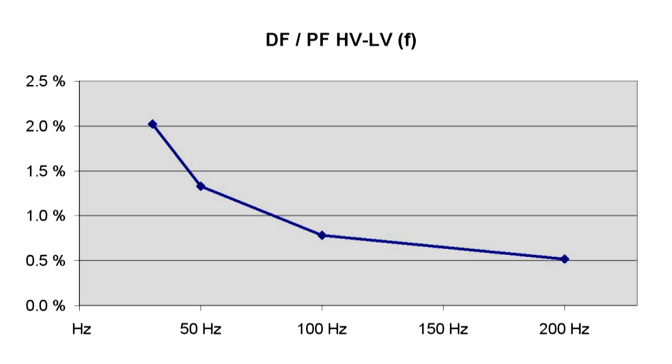The power factor or the dissipation factor at 50 Hz is over 1% and the minimum lies far above 200 Hz. It can be assumed that the insulation contains a relatively large amount of water.